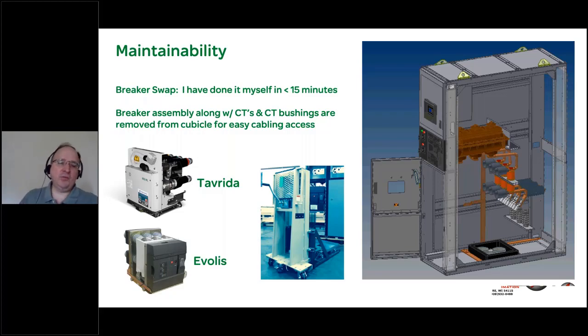There's two different breakers that we do offer for this design currently in the 5 and 15 kV categories, which again is the emphasis of my presentation today. And that is the Schneider Electric Evolis, the French would say Evolis, for that breaker, and the Tavrida arc flash breaker, which is pictured above it. And both of these breakers are available in either fixed mount or draw out applications, and we have installed base references for both of those.